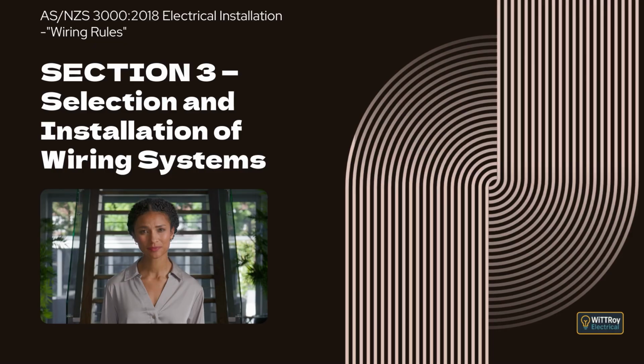This clause explains that wiring systems must be chosen and installed so they work safely and correctly. They must protect people from touching live parts, either by strong insulation or by keeping live parts out of reach. They must be suitable for carrying current, controlling voltage drop, and meeting minimum size rules for conductors. Connections, joints, and terminations must be reliable and electrically continuous. Supports, suspensions, and fixings must be strong enough for the wiring system. The wiring system must suit its intended use, including special situations such as fire resistance, explosion protection, or safety services.